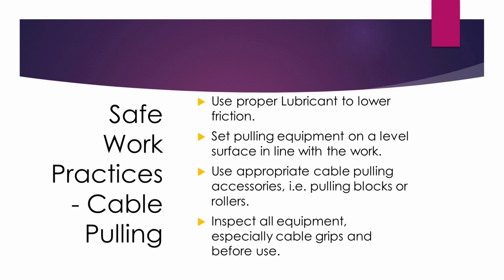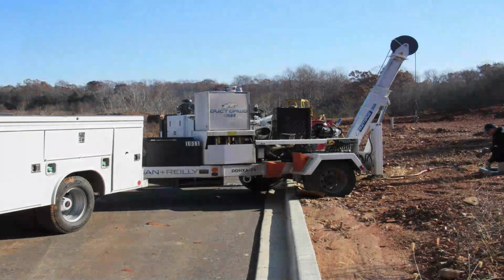Make sure you set your pulling equipment up on a level surface. Use the appropriate or correct type of accessories, your pulling blocks, your rollers, and as usual, something I have to say constantly when I teach OSHA and everything else: always inspect your equipment before you use it. Just inspect it. If it's damaged or defective, don't use it, get rid of it, replace it.